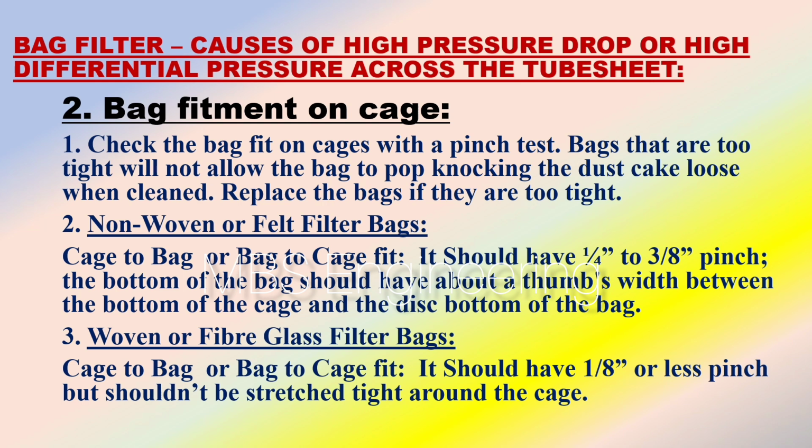Point number 3. Woven or fiberglass filter bags. Cage to bag or bag to cage fit. It should have 1/8 or less pinch but shouldn't be stretched tight around the cage.